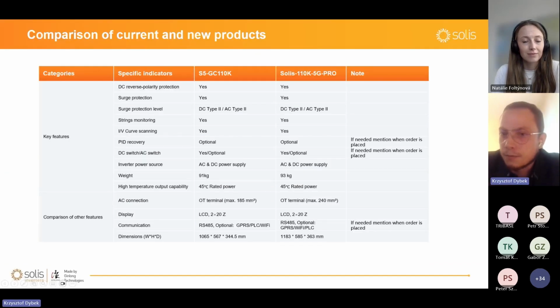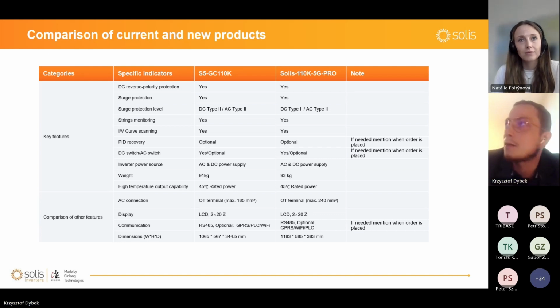So those inverters are pretty much like each other. Pro is better suited, for example, for mixing grid-tied inverters together with older but fully tested RHI hybrid inverters from us. If you have hybrids on site and you want to use zero export limitation, you should use Pro inverter, not the normal one, but Pro, and EPM plus device as a master.